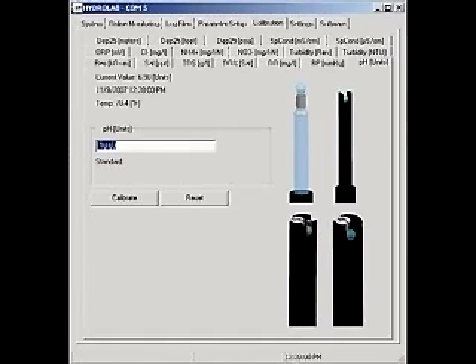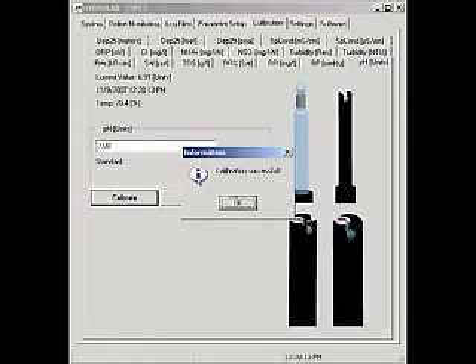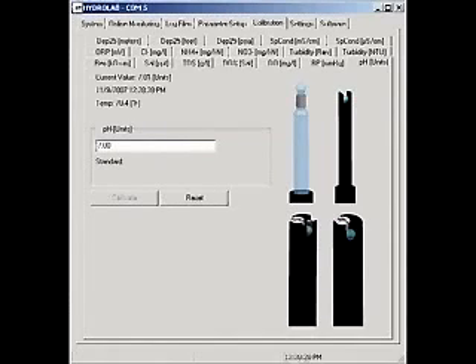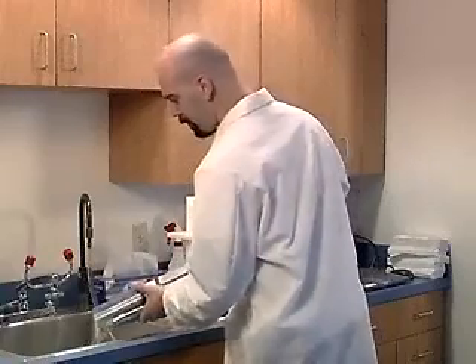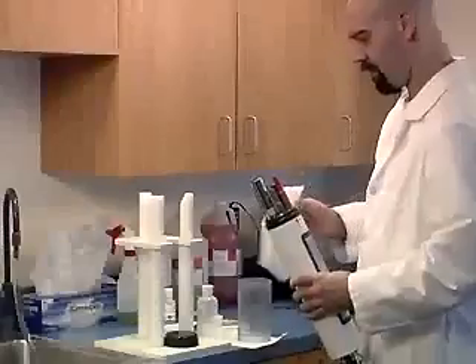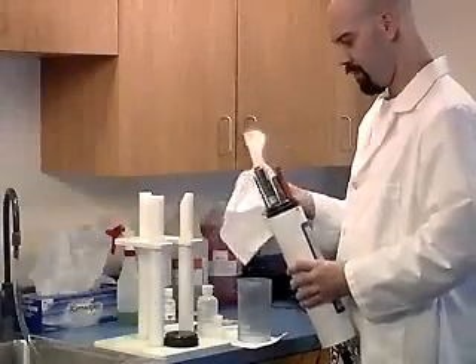When the readings are stable, type a value of 7.00 into the box, adjusted for temperature if necessary, and click Calibrate. A calibration successful message will appear. If the pH readings continue to drift for an extended period of time or jump up and down, the sensor may need to be cleaned or replaced. Pour the buffer 7 out. Rinse the sensors and dry them.